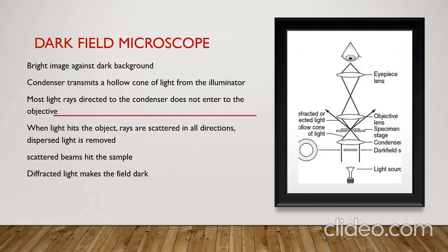In dark field microscope, the field is dark and the image appears bright. Before the condenser there is a dark field stop. The condenser transmits a hollow cone of light into the specimen. From the specimen, the light is scattered in all directions — some of the light enters into the objective lens while most of the light rays are removed. From the objective, it enters into the eyepiece and we can see the image through the eyepiece.